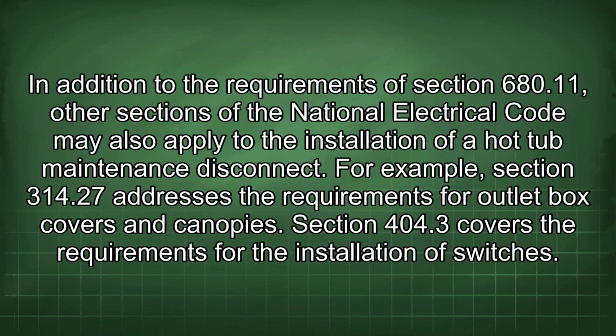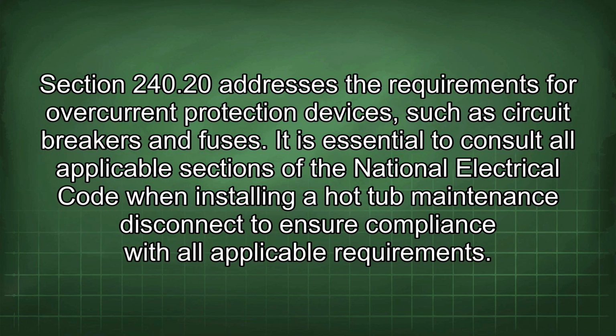In addition to the requirements of Section 680.11, other sections of the National Electrical Code may also apply to the installation of a hot tub maintenance disconnect. For example, Section 314.27 addresses the requirements for outlet box covers and canopies. Section 404.3 covers the requirements for the installation of switches. Section 240.20 addresses the requirements for overcurrent protection devices, such as circuit breakers and fuses. It is essential to consult all applicable sections of the National Electrical Code when installing a hot tub maintenance disconnect to ensure compliance with all applicable requirements.